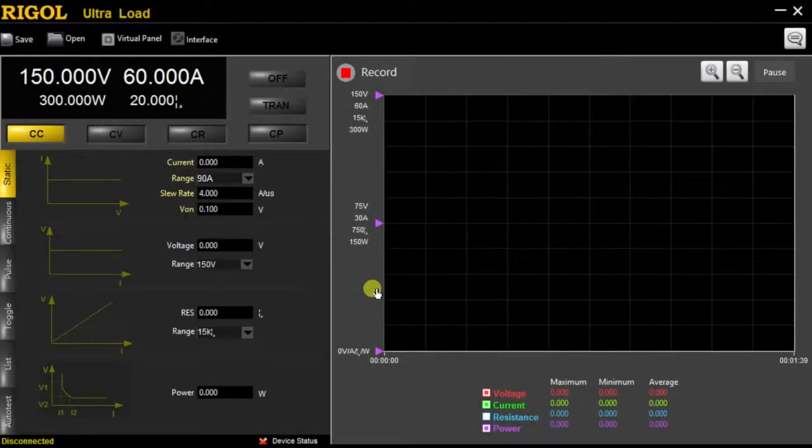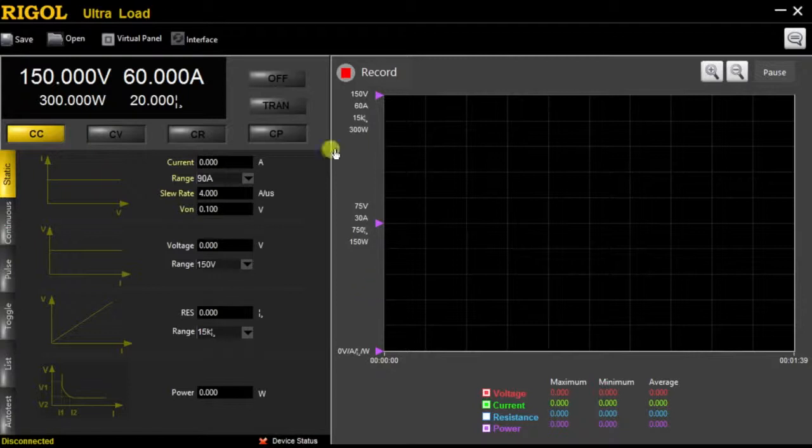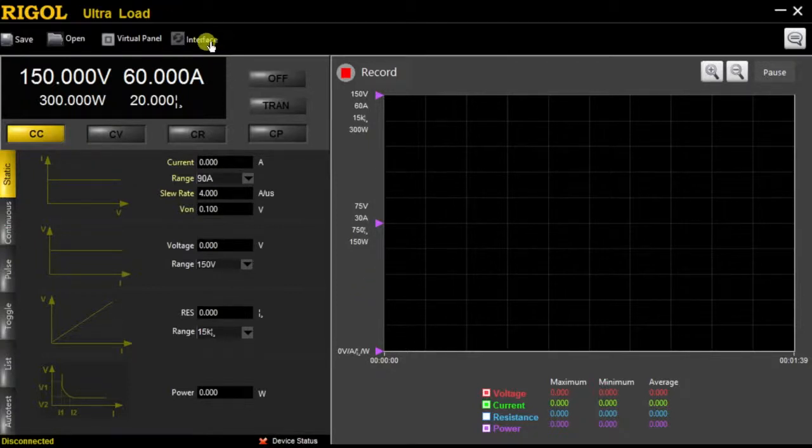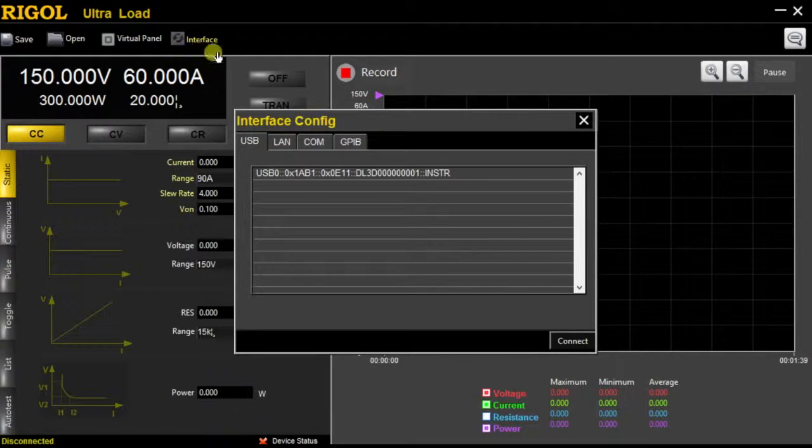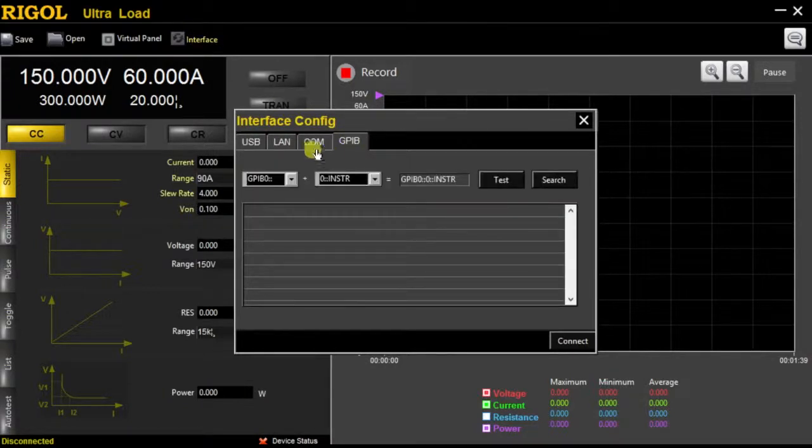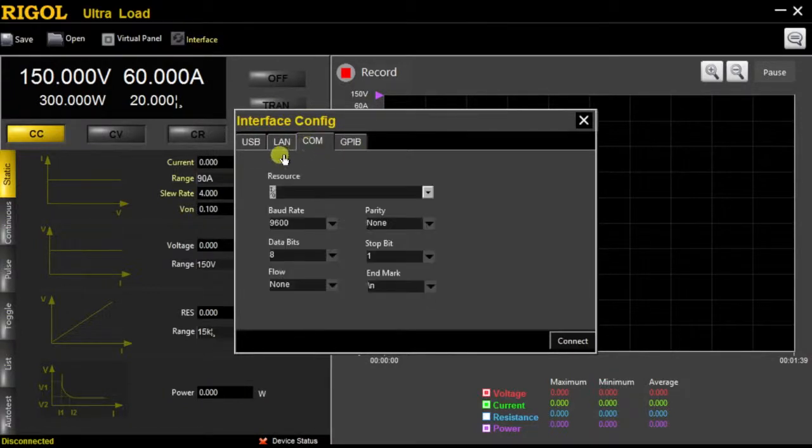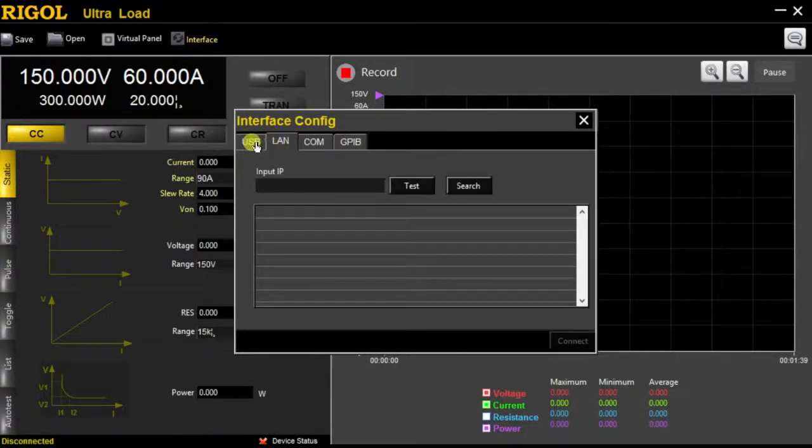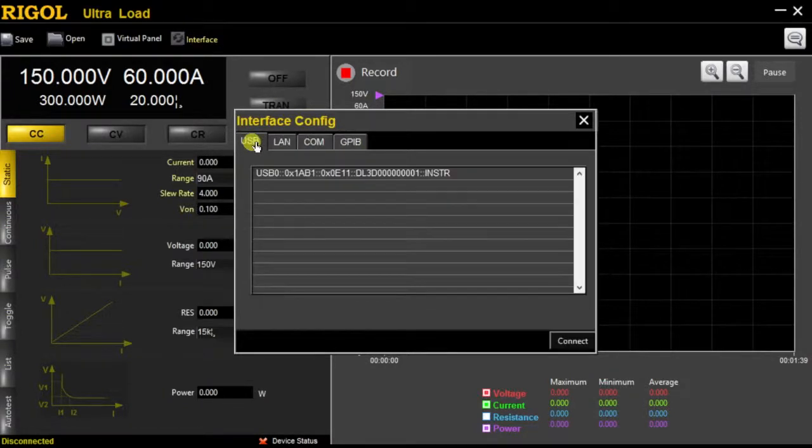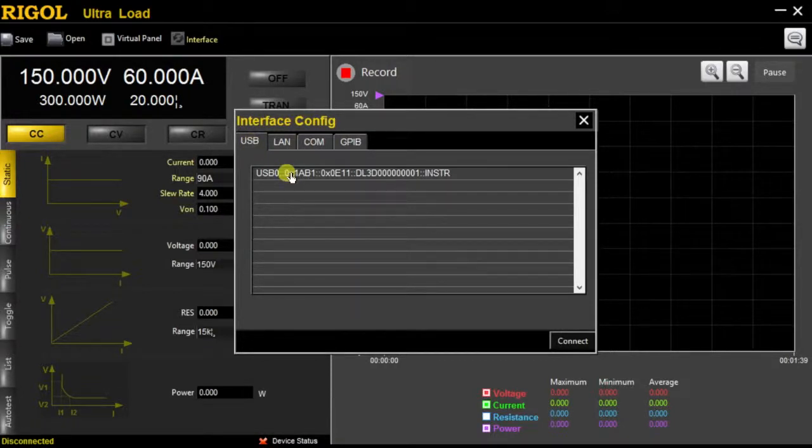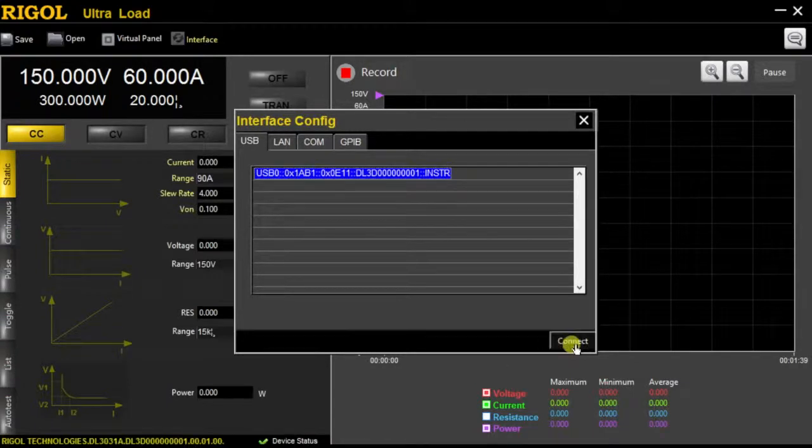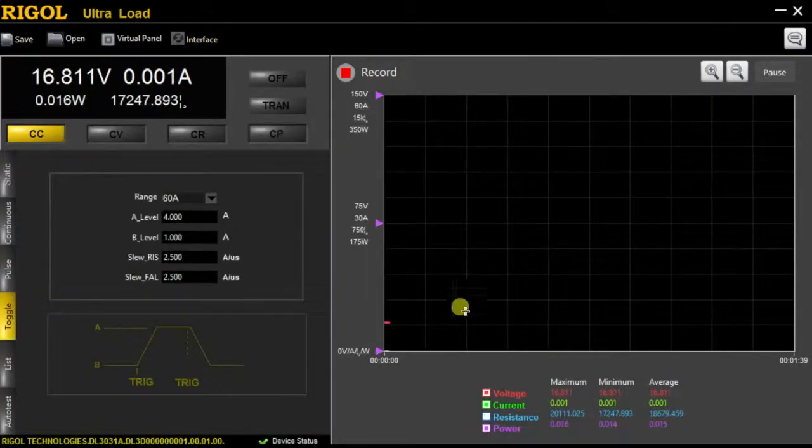To begin with, in order to demonstrate Ultra Load, I'm going to interface the software with the load itself. I just go up here and click on interface. I can choose between GPIB, the communication port, LAN connection, and USB to interface with the software. For this, I'm going to be using the USB port and the cable provided, and then I'm just going to highlight and connect.